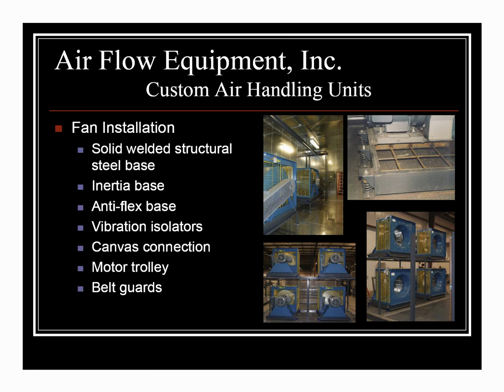Everything's standard mounted on open coil vibration isolators or a seismically restrained isolator, depending on the specification. In the upper left-hand picture you can see 2 fans with belt guards and a motor trolley running overhead. That's one of the things we like to do: when motors get to be, say, 30 horsepower or bigger, with multiple fans like this, we put in a motor hoist rail for maintenance and working on motors, which is very effective.